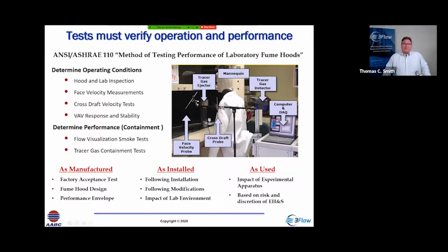We place an ejector inside the hood, we generate a tracer gas, we measure breathing zone concentrations and detect those with a meter that allows us to measure down to 10 parts per billion. With the visual limitation of smoke testing, you can only see about 100 parts per million. So there may be escape from the hood, you just don't see it. But with the quantitative test, we can actually measure it. And these tests can be conducted at the manufacturer, as manufactured, that's testing the design of the hood; as installed, after it's installed, before people use the hood; and then finally during commissioning, and then finally as used, based on risk associated with the application.